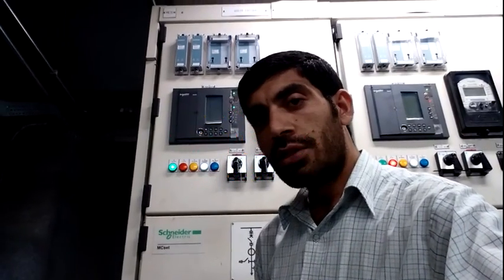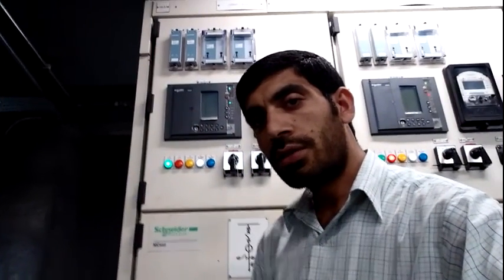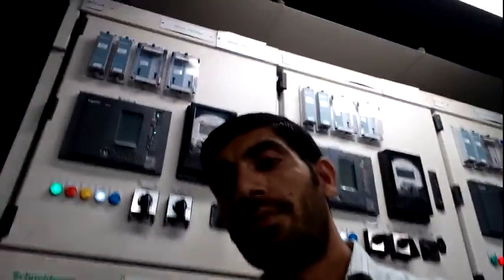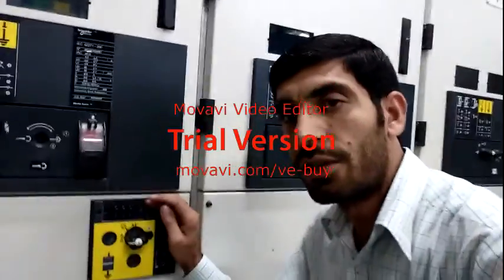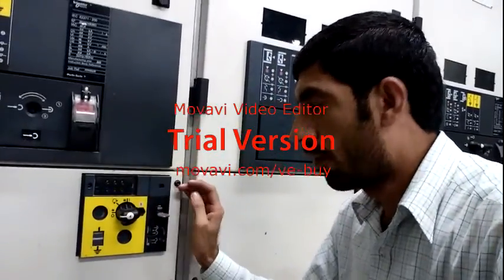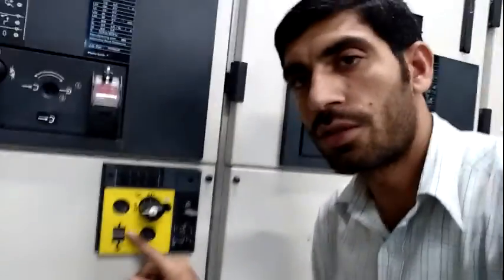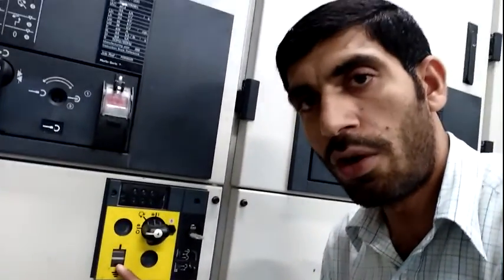First of all, I have two conditions. The first one is the earth switch. If my earth switch is closed, I cannot operate the breaker. I cannot close the breaker. Now my earth switch is open, so I can close the breaker. I can show you here. This one is the earth switch, and it is in open condition. So I can close the breaker.